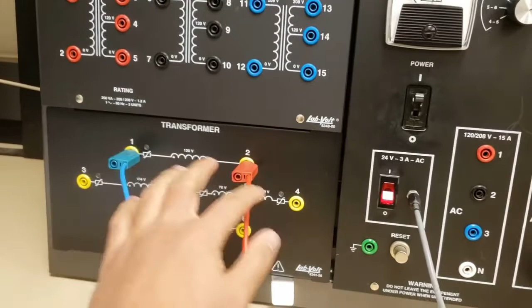I was going to say that the open circuit test has its limitations - this is where it has its limitations. The values you calculate here are just for that voltage you're applying. If you half that voltage, ideally it would result in the same RC and XM. Indeed, if you had the given RC value and the given XM value, regardless of the voltage you put in, they should stay the same - they're not going to change with voltage. That's what you have with linear devices.